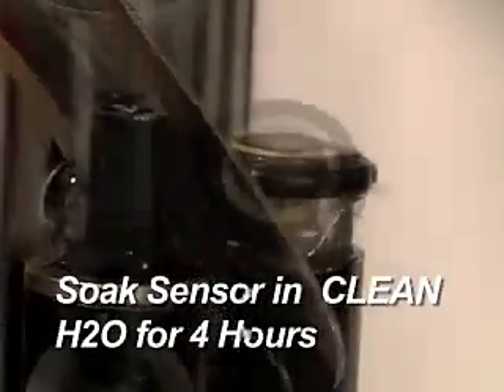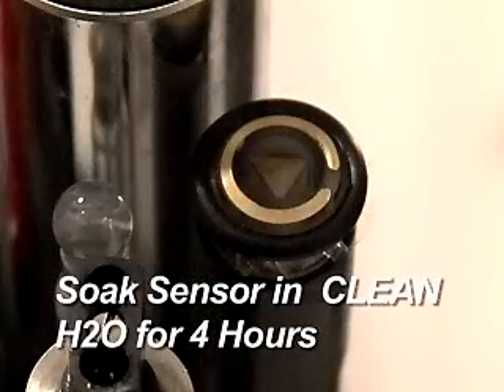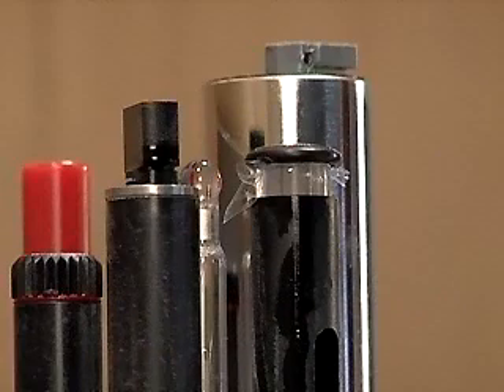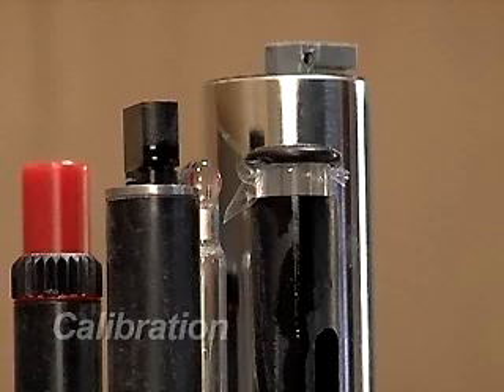The sensor must soak in clean water and the membrane allowed to relax for a minimum of 4 hours prior to calibration. The dissolved oxygen readings will drift if the sensor is calibrated early. The Clark cell is now ready to calibrate. To obtain accurate dissolved oxygen readings, the conductivity sensor must be calibrated before the Clark cell is calibrated.